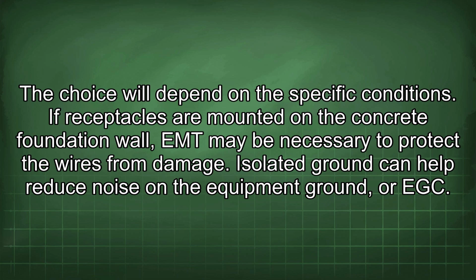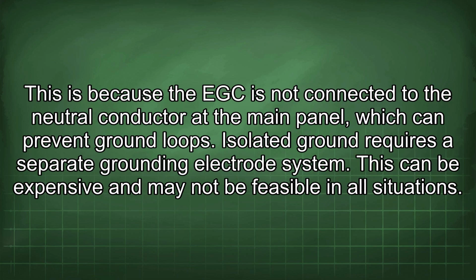Isolated ground can help reduce noise on the equipment grounding conductor, or EGC. This is because the EGC is not connected to the neutral conductor at the main panel, which can prevent ground loops. Isolated ground requires a separate grounding electrode system. This can be expensive and may not be feasible in all situations.